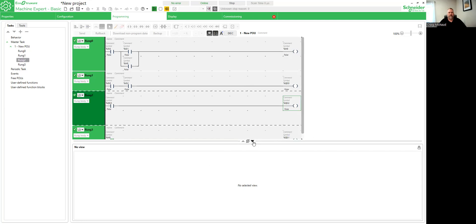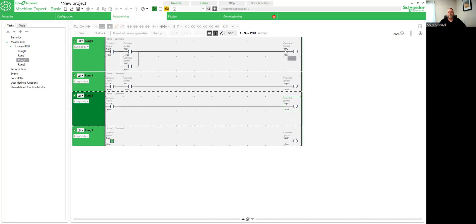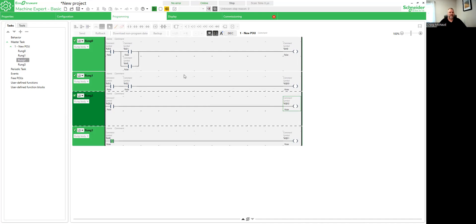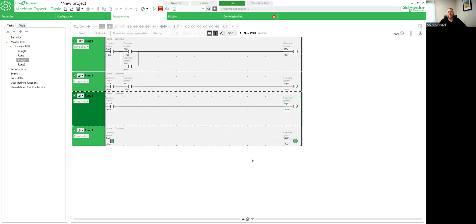But the nice thing is with this here, we would have to have four outputs if we use the coil, but I was able to only use the three outputs and those are lights with no coil because internally in the controller, the memory bits actually work like coils, but they're really not so it kind of confines things. There's a lot of memory bits that are in the units itself that by programming it this way, we're using less output. So you don't need a huge controller to control a lot of coils. You may only need a smaller amount. And when you think of cost of the PLC, that's definitely something, not the PLC program, but using the PLC as the device that's going to control your unit automatically. I mean, that's something you definitely want to think about because if you're dealing with a unit that could cost you two, three, 400 bucks, but you have 17 outputs, well, now you got to get a bigger controller that I think could cost you anywhere from 800 to $1,000.